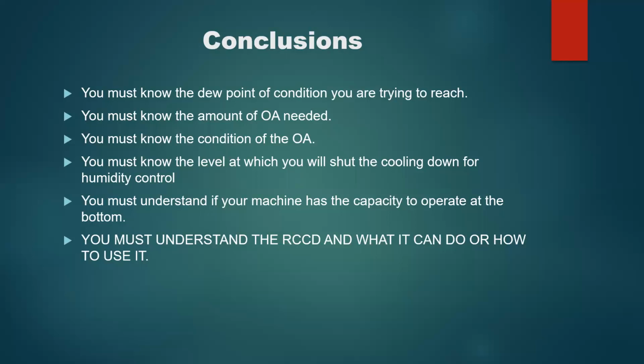And now when you hit the bottom, the RCCD will take over as long as the line size on a split system is okay. And as long as everything else is set up, as long as you meet all the requirements, now that machine can operate even down to 8 tons or so. And that's critical. So what happens? Those are the things and the conclusions of this video.